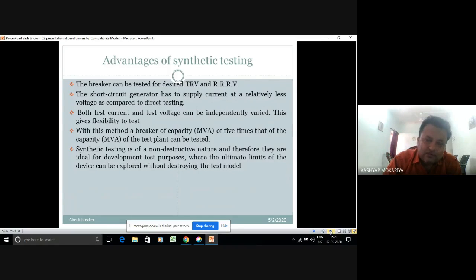Advantage of synthetic testing: the breaker can be tested for the desired TRV and RRRV, transient recovery voltage and rate of rise of recovery voltage. The short circuit generator has to supply current at a relatively lower voltage as compared to direct testing. Both test current and test voltage can be independently varied. With this method, a breaker capacity of 5 times that of the test capacity can be tested. Synthetic testing is non-destructive in nature, and therefore ideal for development test purposes, where the ultimate limits of the device can be explored without destroying the test model.